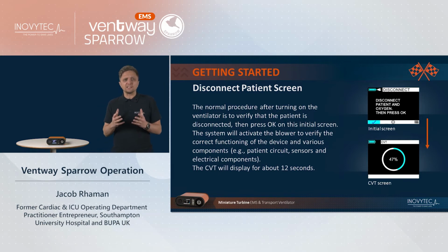The entire test should only take around about 12 seconds. This will be indicated by a percentage wheel on the circuit verification test. Once the test is complete and passed, the ventilator is now safe for use. We will cover test failure and reasons for it later on during this session.